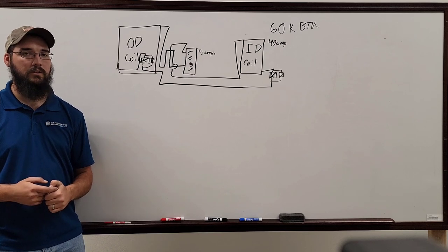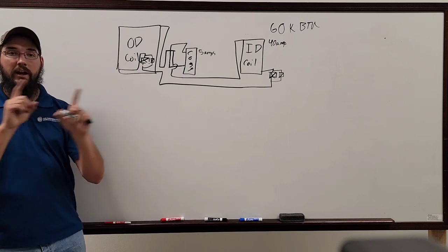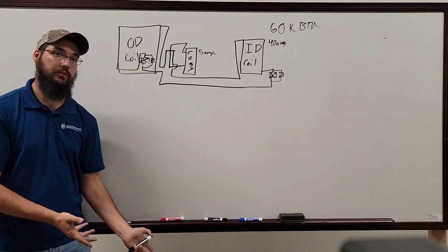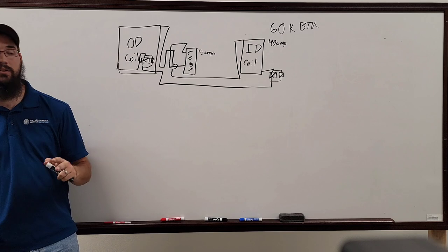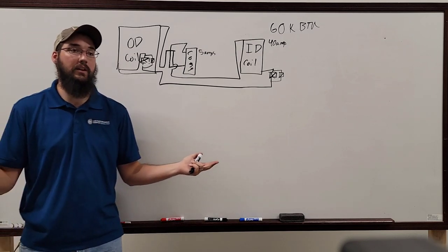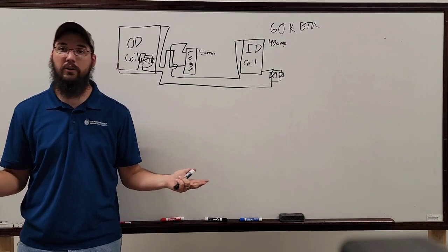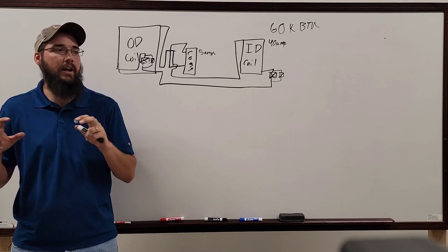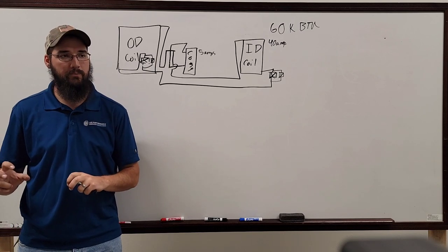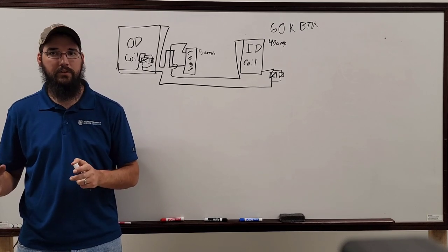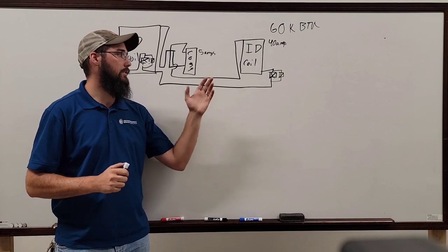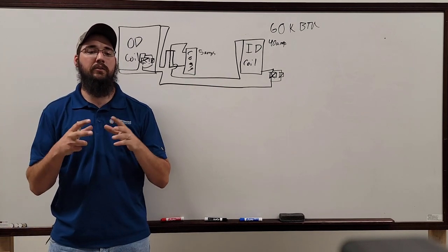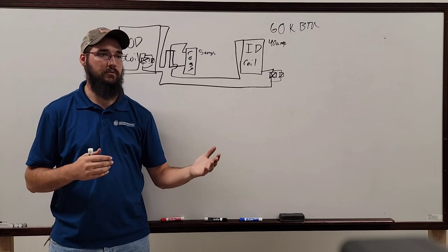Yeah. Now, a counteracting factor, keep in mind, is that the air coming in is colder. So if the house is cold, let's say it's 60 degrees in the house because the unit quit working, well, you've got colder air, so that's going to mitigate some of that high head pressure issue a little bit. But you still have to control the amount of heat exchange happening.